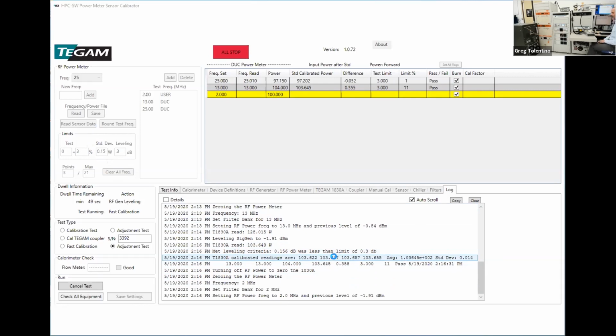If for some reason, let's say it was an amp whose gain changes substantially as its temperature warms up, or maybe one of the filters' gain or insertion loss changes as it warms up, sometimes you have to wait a few minutes to stabilize the power well enough to use it for calibration. And this check makes sure that you don't accept it too early. Sometimes you'll see it collecting a new set of data, saying the standard deviation was too high. I'm going to add a few more points to the list and wait till everything is stable. All right, so we've passed and moved on to the 2 megahertz point.